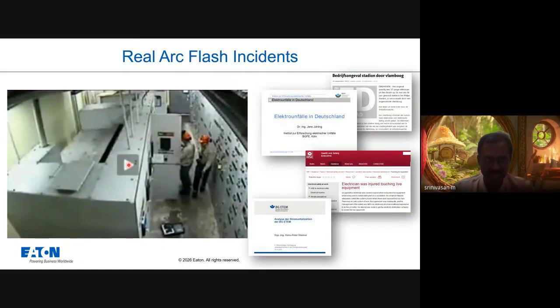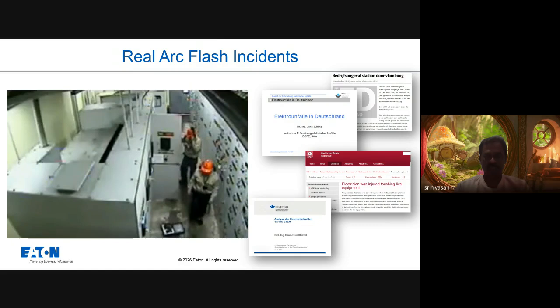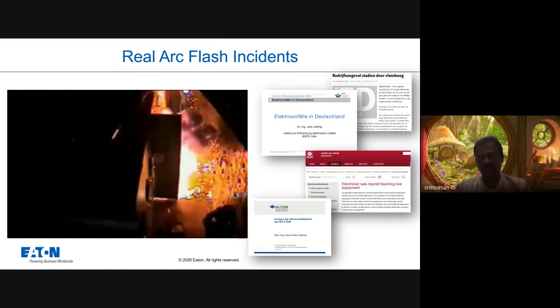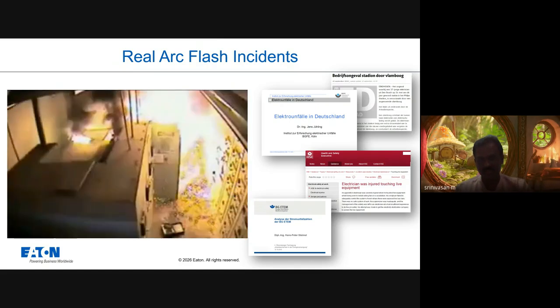I will show a small video, which I took from YouTube, showing the consequences if the switchboard is not type tested for internal arc. This is a real arc flash incident. You can see the impact of the internal arc. It threatens the life of the human being, the operating personnel, and also the switchboard. So internal arc is a very critical requirement for the switchboard system.